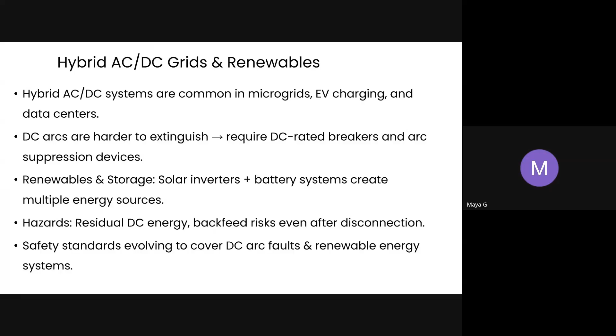When we consider renewable and storage, mostly solar is there, so solar inverters plus battery systems create multiple energy sources in the grid. There will be residual DC energy which may backfeed even after disconnection, so safety standards need to evolve to cover this backfeeding or DC arc fault.